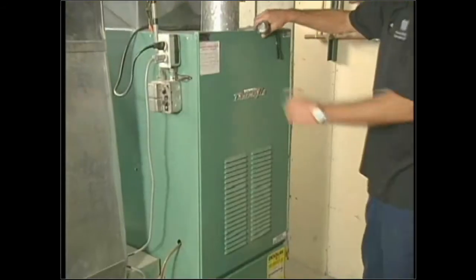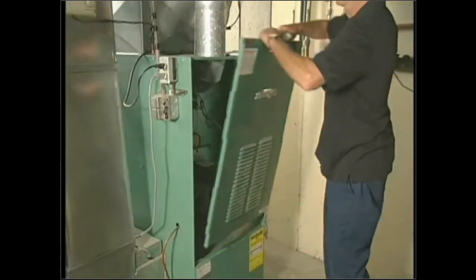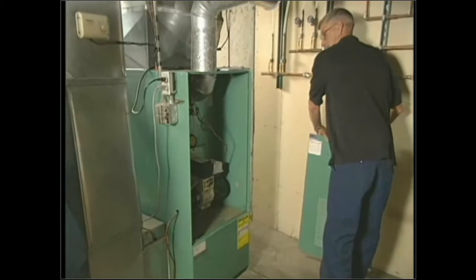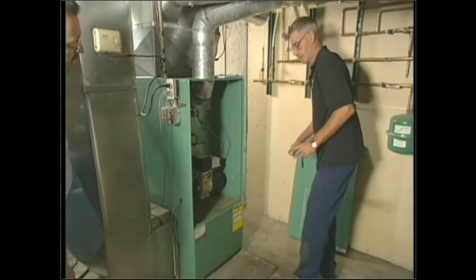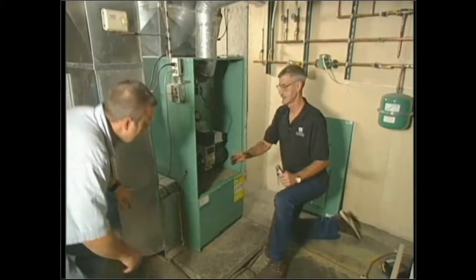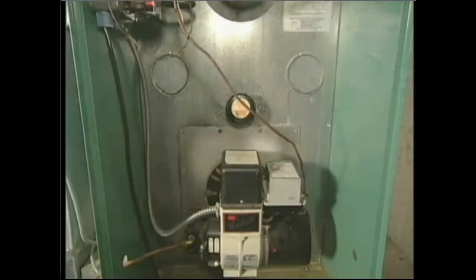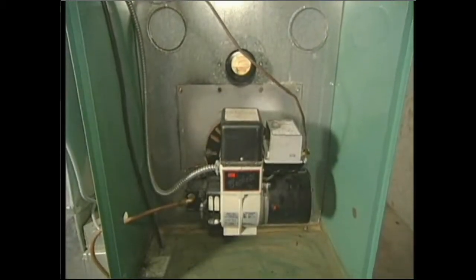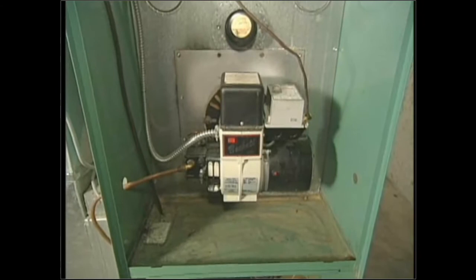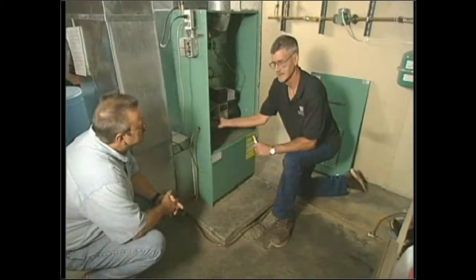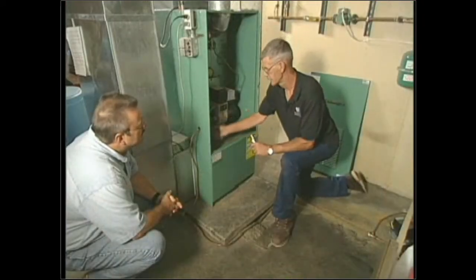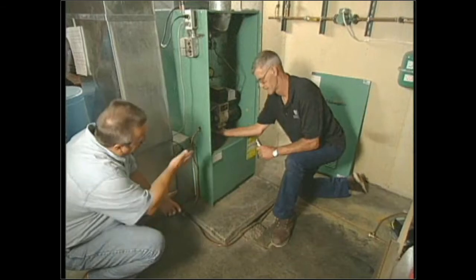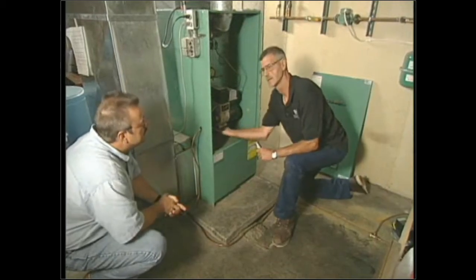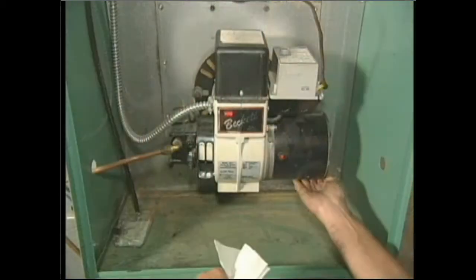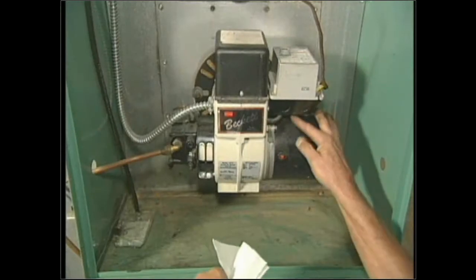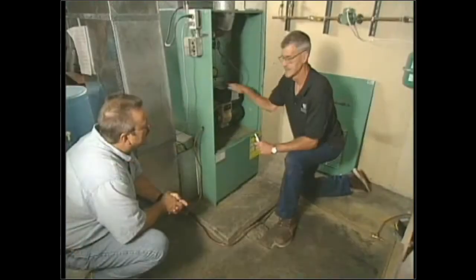Continuing with the visual inspection, an auditor should also start looking inside of the cabinet. What I look for, and what an auditor should be looking for when he does this too, is the same thing we did everywhere else: dust and debris across the bottom of this decking, or oil underneath the connection here. That means there might be a small oil leak here. Maybe a good idea to take a napkin or a paper towel around there? Yep. Another thing we'll do is we'll check underneath the burner itself here to see if there's anything built up, because if there's oil or something down here, that means that this is improperly pitched.